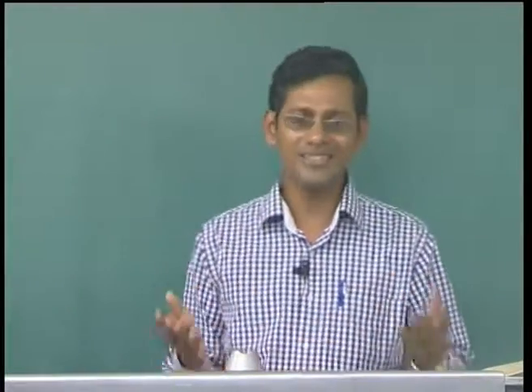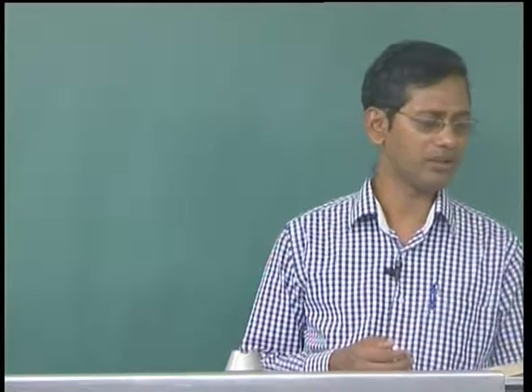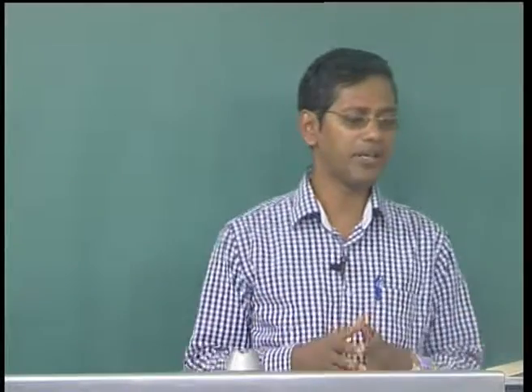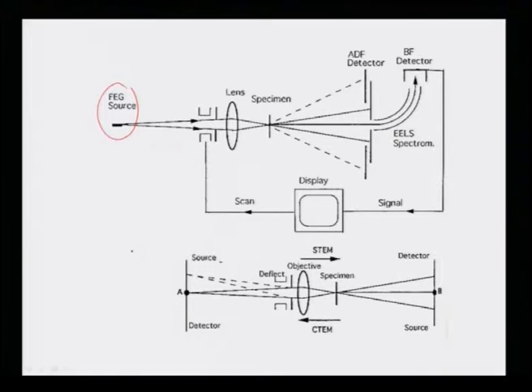The components in a scanning transmission electron microscope are more or less the same as in a conventional TEM — not much difference. The key addition is a scanning coil which makes the beam scan the sample in raster mode, just like in a scanning electron microscope. There are practically many advantages to using STEM.